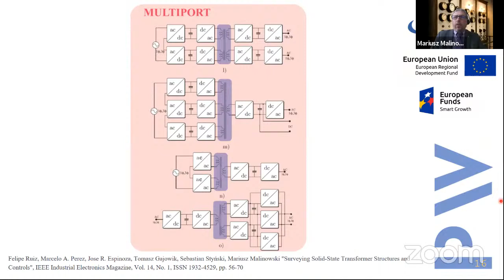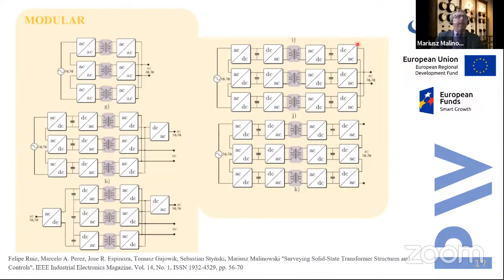The last group of solid-state transformers are called modular, because they present a modular architecture. We have multiple DC-DC converters with single phase transformers, used for the future composition of the solid state transformer built from modules. However, the most popular are two topologies: the modular multi-level converter, where the solid state transformer is built on that, or the one where we have cascaded connected converters on the medium voltage side and parallel connected converters on the low voltage side.